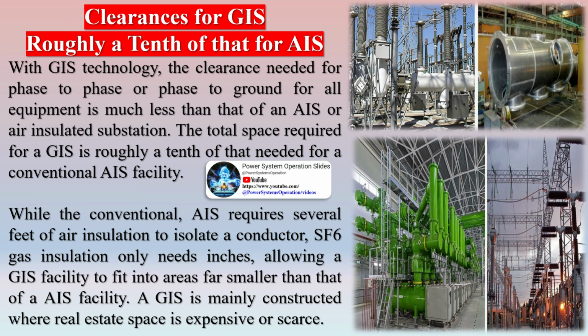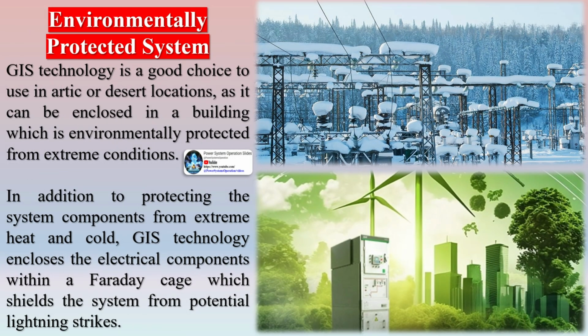With GIS technology, the clearance needed for phase-to-phase or phase-to-ground for all equipment is much less than that of an AIS, or air-insulated substation. The total space required for a GIS is roughly a tenth of that needed for a conventional AIS facility. While the conventional AIS requires several feet of air insulation to isolate a conductor, SF6 gas insulation only needs inches, allowing a GIS facility to fit into areas far smaller than that of an AIS facility. A GIS is mainly constructed where real estate space is expensive or scarce.